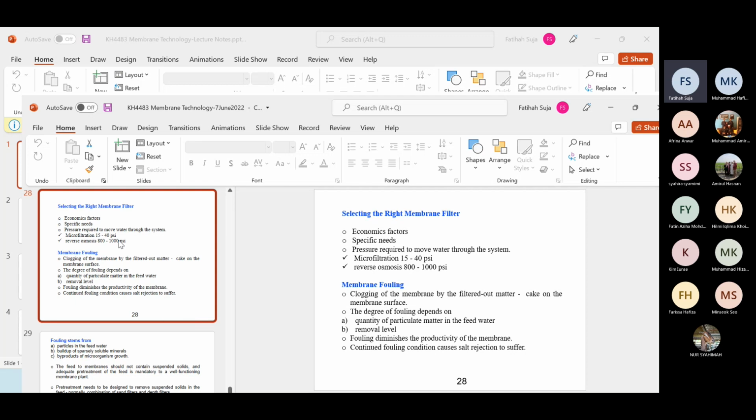Even though you know that a reverse osmosis filtration system will remove many substances from the water, it is much more expensive to build and to operate compared to a microfiltration facility. Since a microfilter has much larger pores, the system can operate at much higher flow rates and much lower feed pressures. So this is why you need microfiltration. More flow and less feed pressure mean smaller facilities that use less energy to produce each gallon of water.